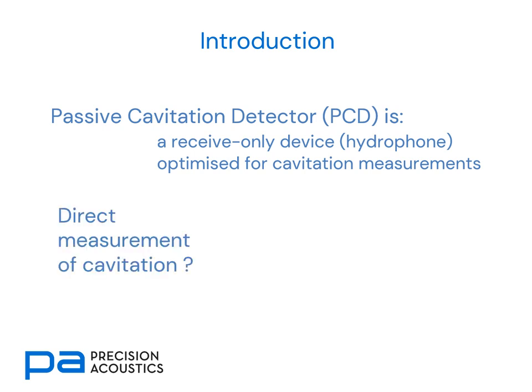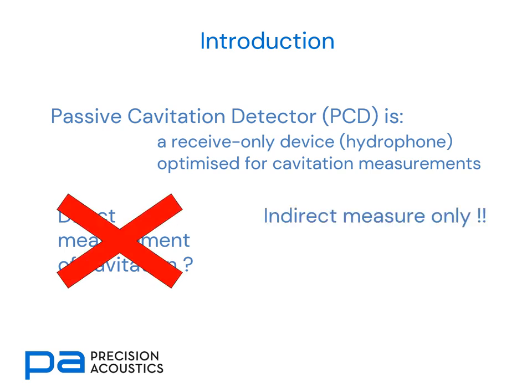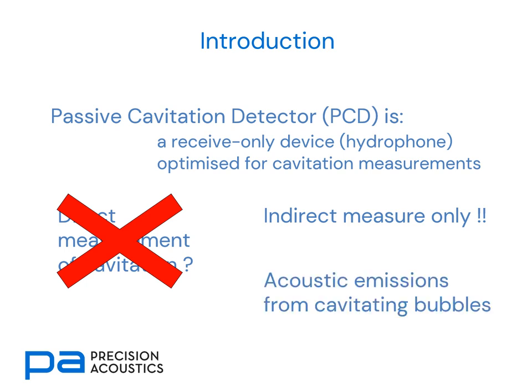I'm often asked: is it a direct measurement of cavitation? To which the answer is sadly not. All that we can do is undertake an indirect measurement. In practice, what we're doing is listening for the acoustic emissions from cavitating bubbles.